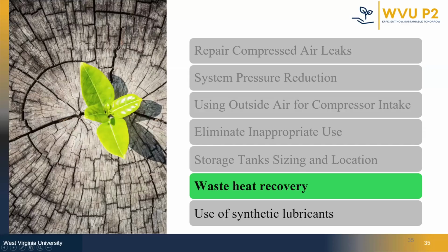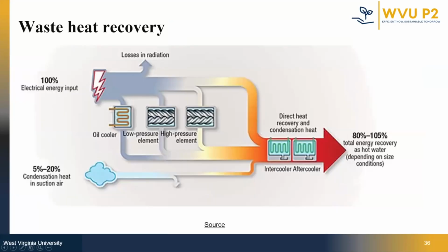Now let's move on to waste heat recovery from the compressed air system. Almost all of the energy that goes into running a compressor eventually becomes heat. We are talking about 90 to 95%. And in most facilities, that heat just gets dumped into the atmosphere and wasted. But instead of letting that energy disappear, we can capture it and use it productively.